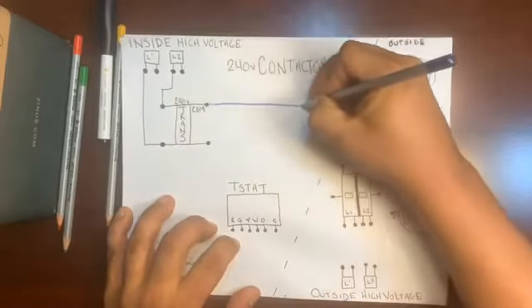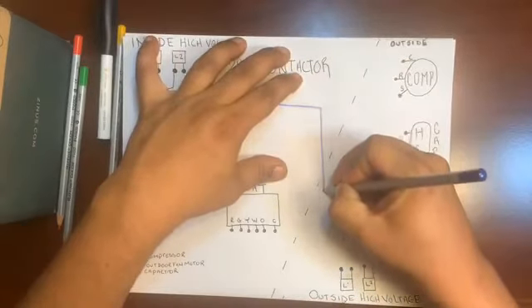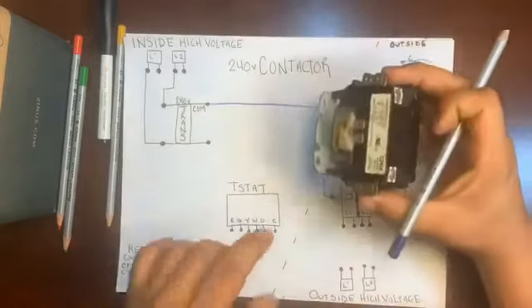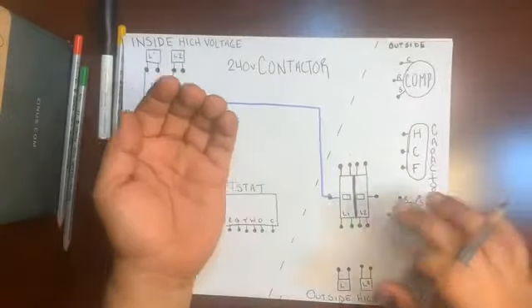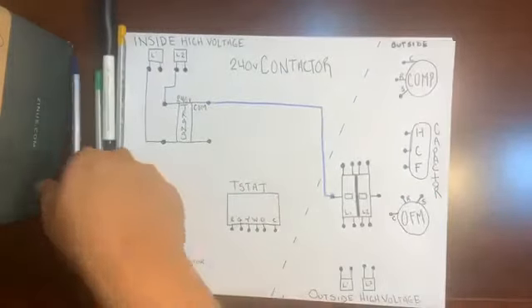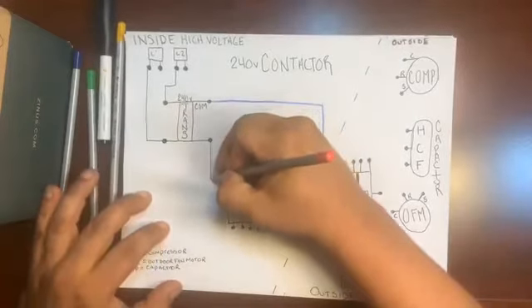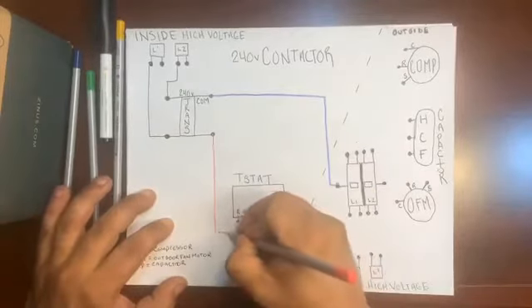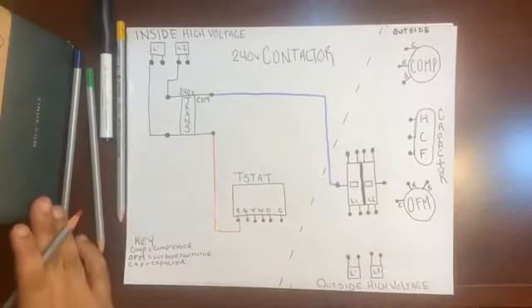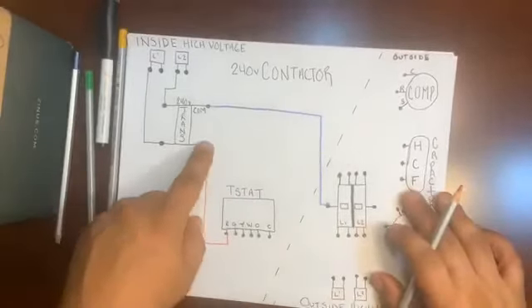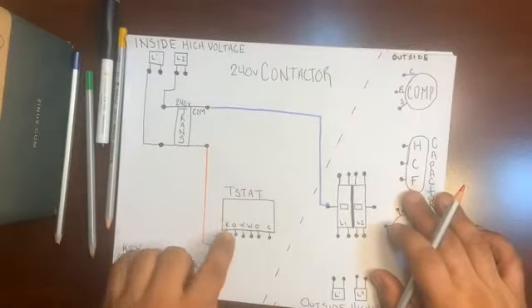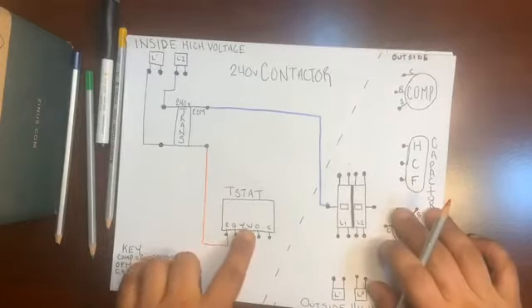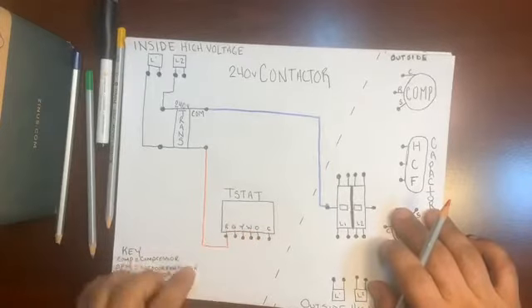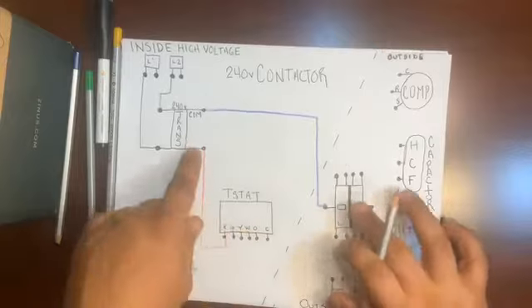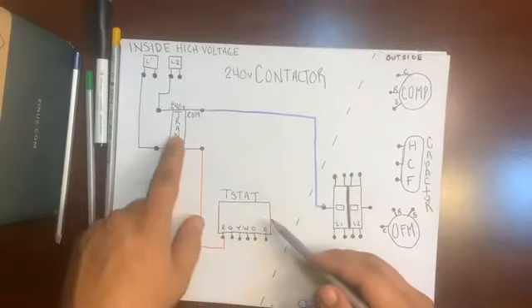This will be a quick one because we only have one relay. I'm gonna start with our common that goes, of course, to one side of our transformer. Put the common in my hand every time. We'll start with that notion. What's next? Let's get the control side. As we've agreed before, bring it directly down to red to feed the thermostat. Because as we agreed before, the thermostat is fed 12 volts from the control side, and then it manipulates the 12 volts to send it to the green for the fan motor, the yellow for the compressor contactor, the white for the heat sequencer, the orange for the reversing valve, and of course, C was our common. Red will only jump into these four to activate the relays. Red will never touch common because that will short out this transformer.